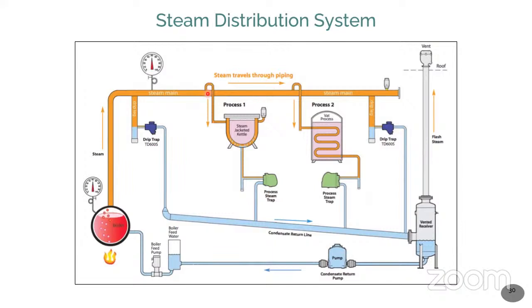So normally the higher pressure is available here, and slightly lower pressure will be available to the second process, and over the entire steam length, the pressure should be optimized. Okay, we cannot avoid the pressure drop, but it should be minimum.